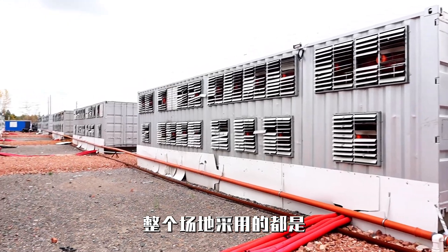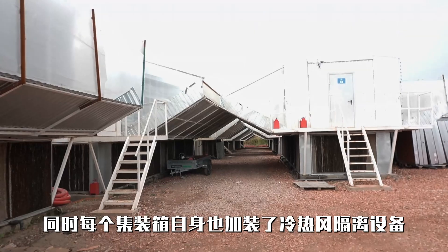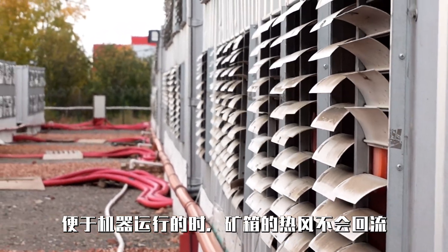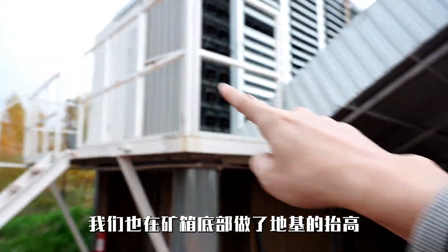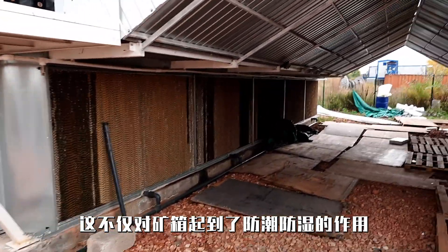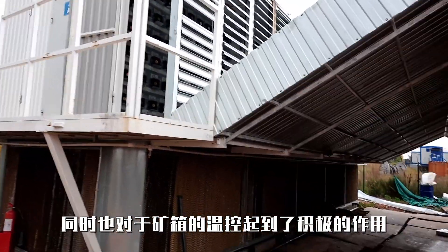Building a bitcoin mining facility near a substation has become one of the most popular methods today, as this model not only saves construction costs but also enhances the stability of the power supply. However, this construction approach poses a comprehensive challenge for bitcoin mining companies. The entire mining site employs a modular container solution, with each container safely spaced apart and equipped with thermal insulation devices for hot and cold air, preventing hot air from the mining machines from recirculating. We have raised the foundation of the containers and installed wet curtains for secondary cooling of incoming air, protecting containers from moisture and dampness while contributing to temperature control.